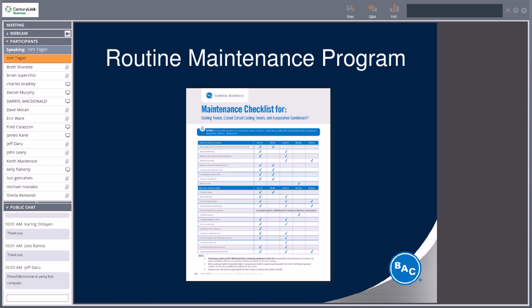Inspect the unit finish. You want to make sure that you're not getting any corrosion from the outside, depending on where it's located. If you're right on the water, your chemical treatment may be fine, but you may be giving your tower a salt bath, depending on how close to the ocean you are. Check your belt condition, adjust the belt tension if necessary.